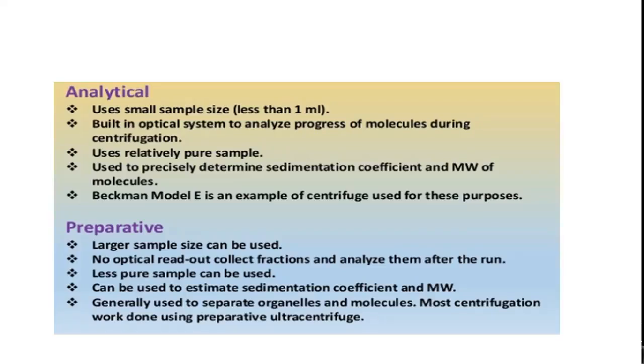Preparative centrifuges generally have a larger sample size. There is no readout system and no real-time monitoring, so you cannot analyze the sample during the run — analysis can only be done after centrifugation is complete.